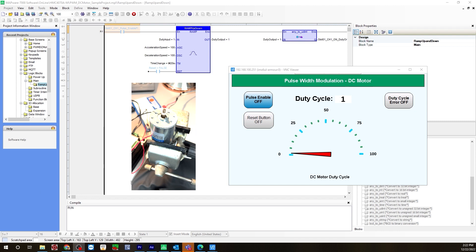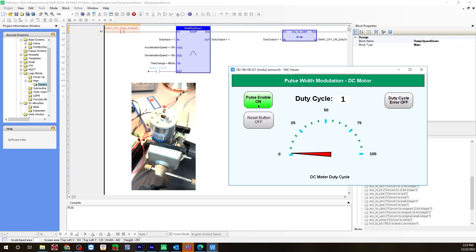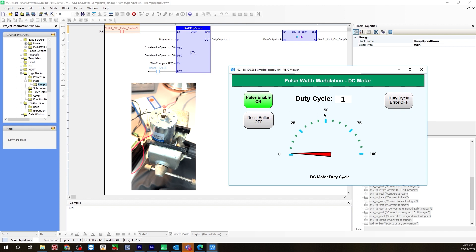I am now online and looking at the logic as well as VNC viewer, which is the view of the user interface on the HMI device itself. Right here is a camera feed of the actual 24 volt DC motor. Now, to turn the motor on, I'm going to enable the pulse. As you can see it's set to one duty cycle. I'm going to demonstrate a gradual acceleration up to 50 duty cycle. I have the acceleration speed at 100, and deceleration speed at 100, and the time is set to 20 seconds. It will take 10 seconds to get up to 50, and it will take 10 seconds to go down back to 1 or 0. Let's demonstrate that now.